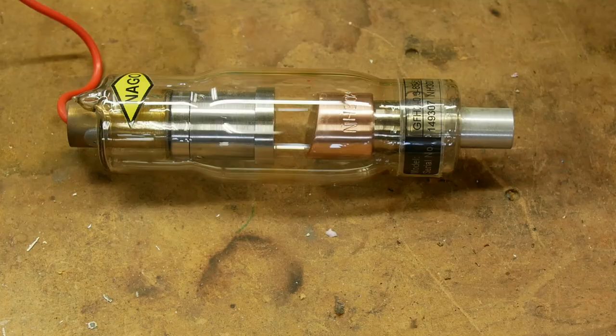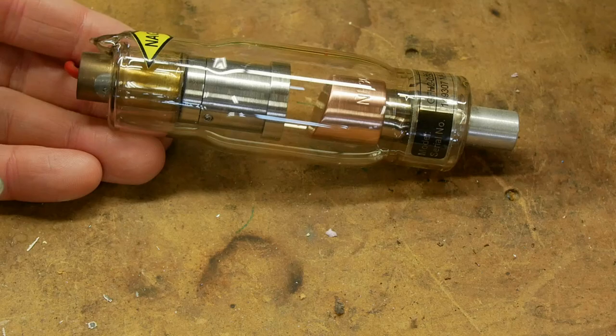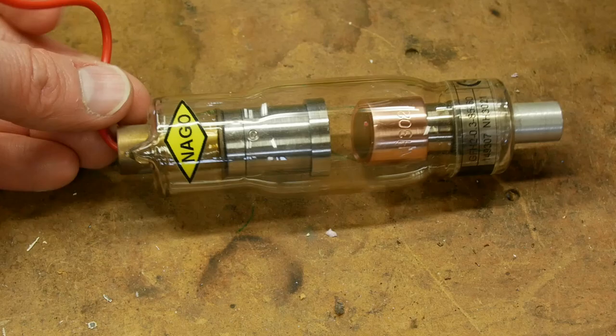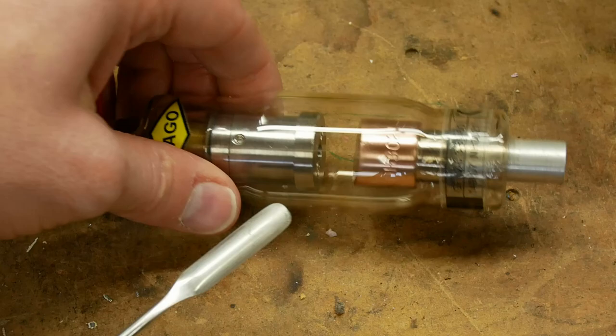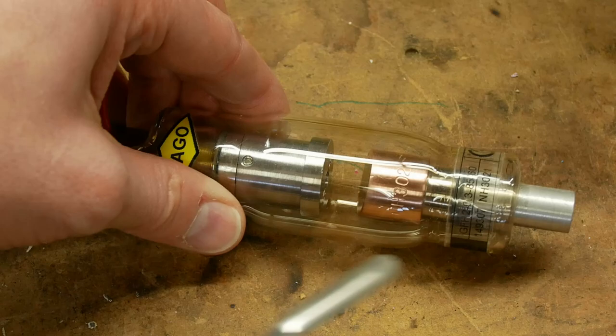Here's a look at an X-ray tube. This is very simple, just a three-terminal device, and what we do is put a high voltage across the tube so that there's maybe 50,000 volts between this terminal and this terminal, and nothing happens yet because there's no electrons to be accelerated. So the next thing we have to do is put a low voltage across these two terminals from the wire to here, and what that does is heat up a filament inside here, and the filament boils off electrons, which are accelerated by this high voltage. And when they slam into the target here, X-rays are produced.